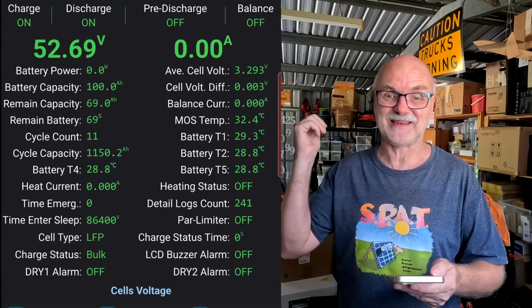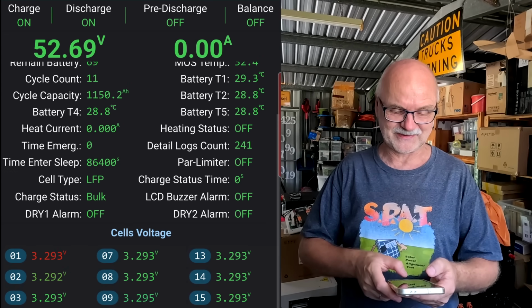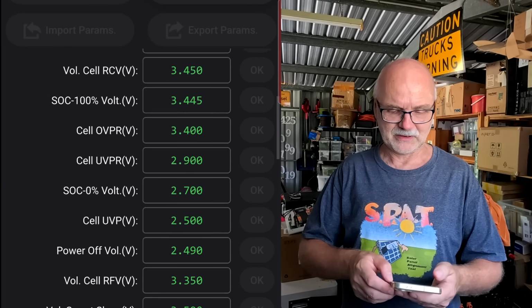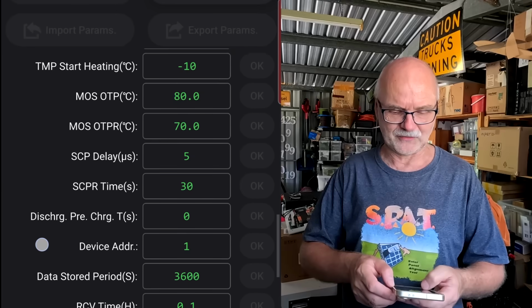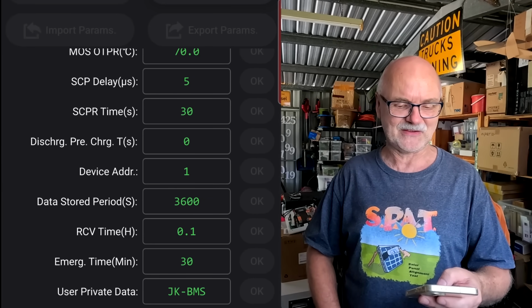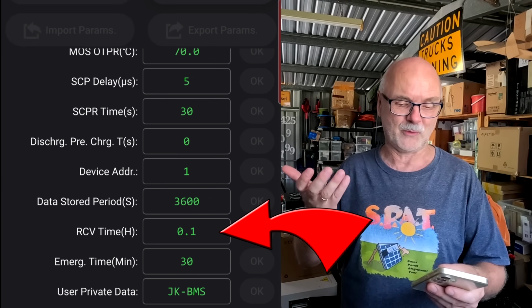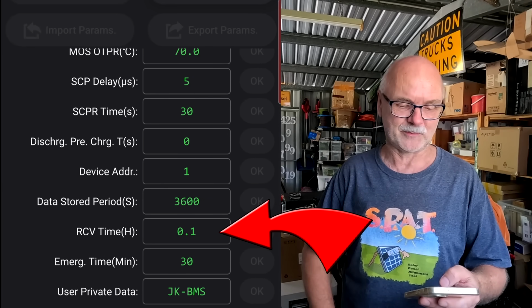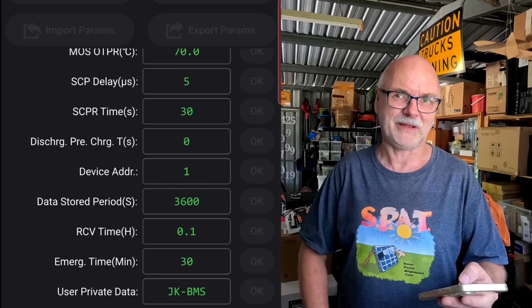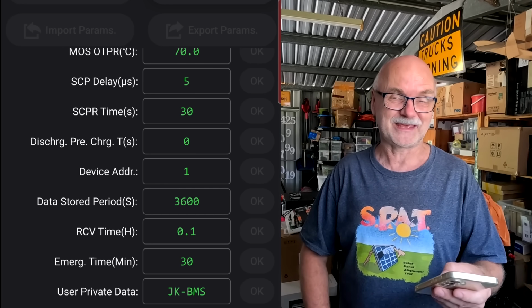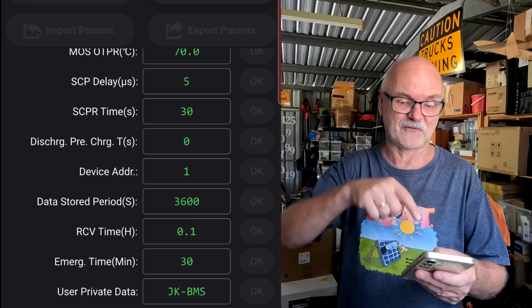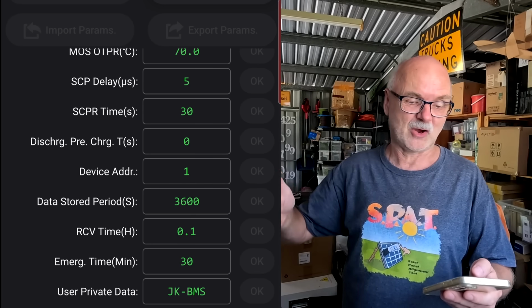At the moment we've got slave number 1 here. If we go into settings, advanced settings, and a bit further down we can see an RCV timer, sitting on 0.1 hours here for testing purposes. This is the bulk, or better, absorption timer. So we keep the voltage at 55.2 volts for 0.1 hour, and then we go back to the float voltage.